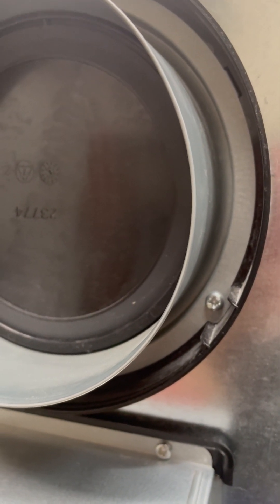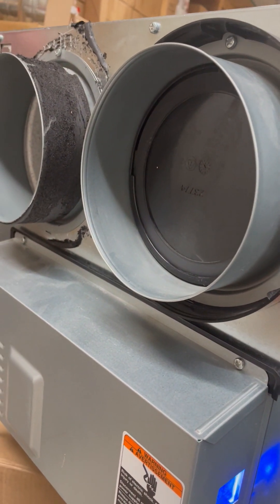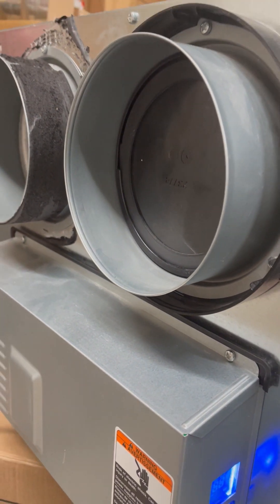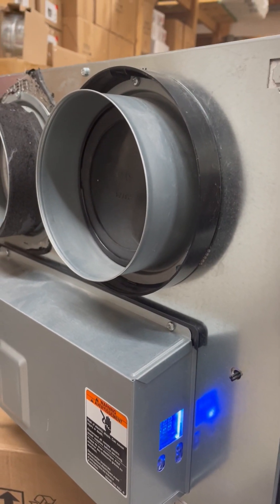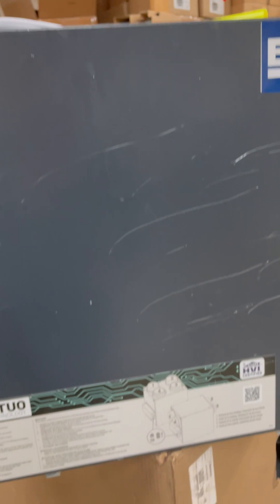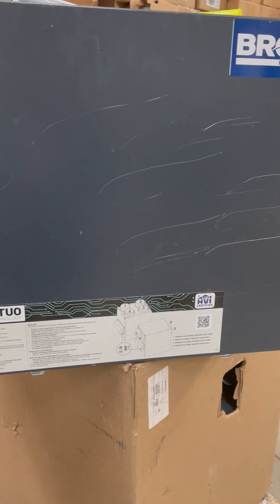There's a flap here. When it closes like that, what that means is it's in recirculation mode, which basically means your bathroom air can go to the bedroom. That just helps defrost things, because your bathroom air is warm, so if that closes when it gets too cold outside, then the heat exchange core there is warmed, and therefore you don't lose the air movement.